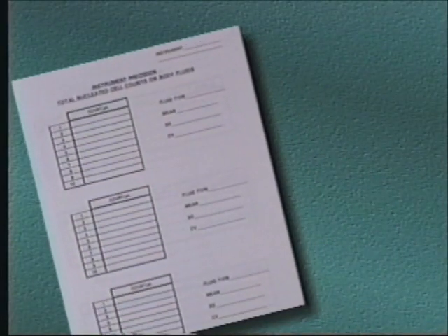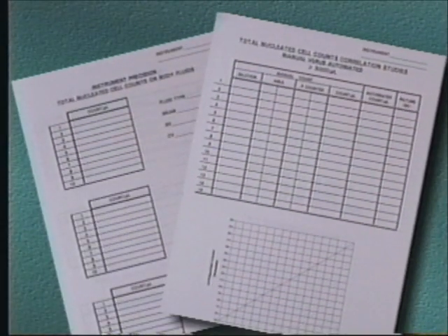Included in the handout are documentation forms to use as you gather the information. You should do precision studies on your instrument following the same method you use for doing precision with whole blood. Also, for fun, you can do precision of the manual method. It may be a real eye-opener to see the results.